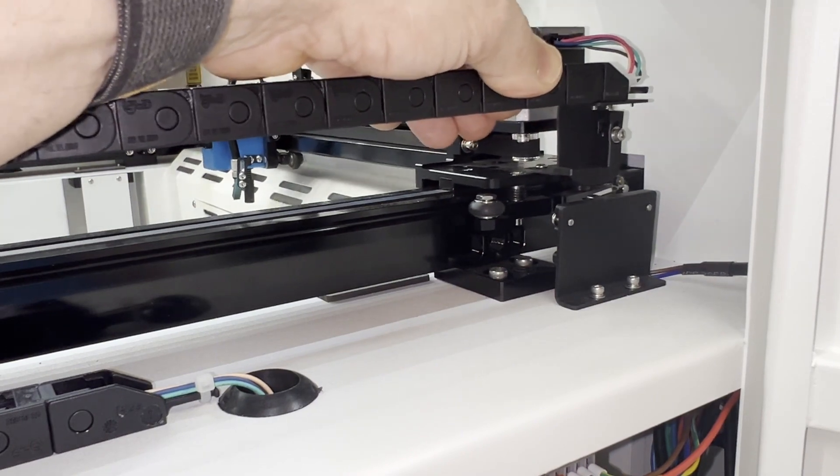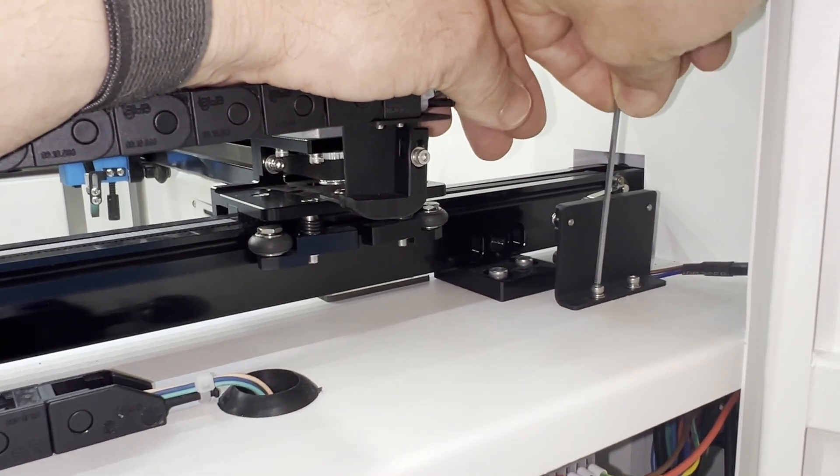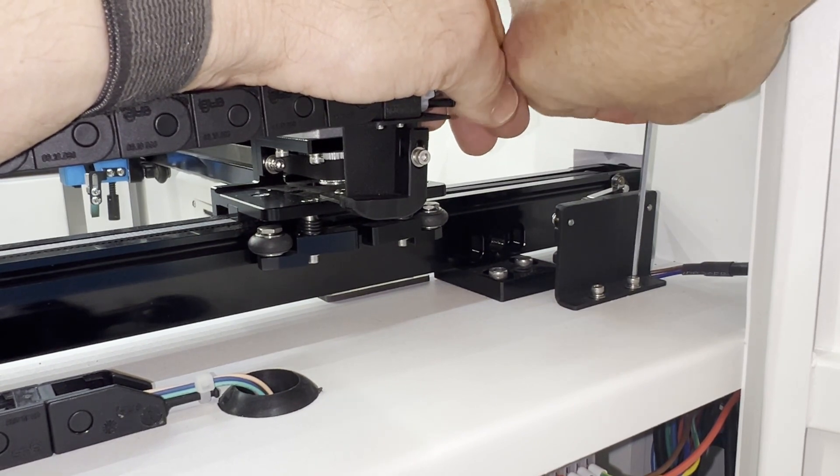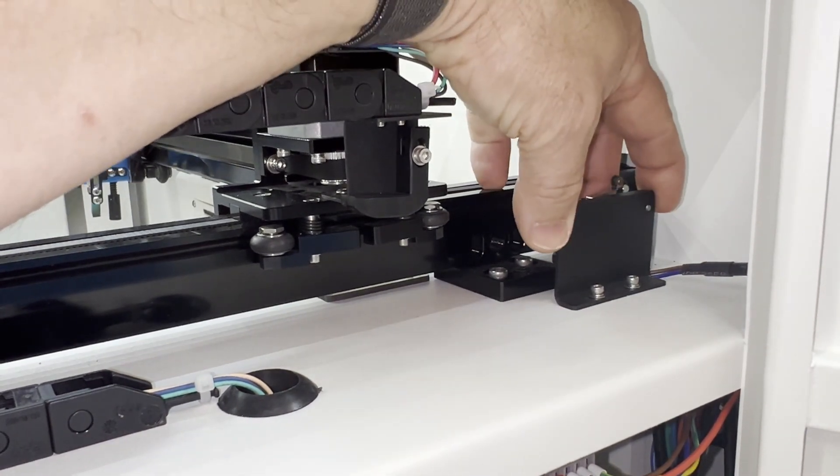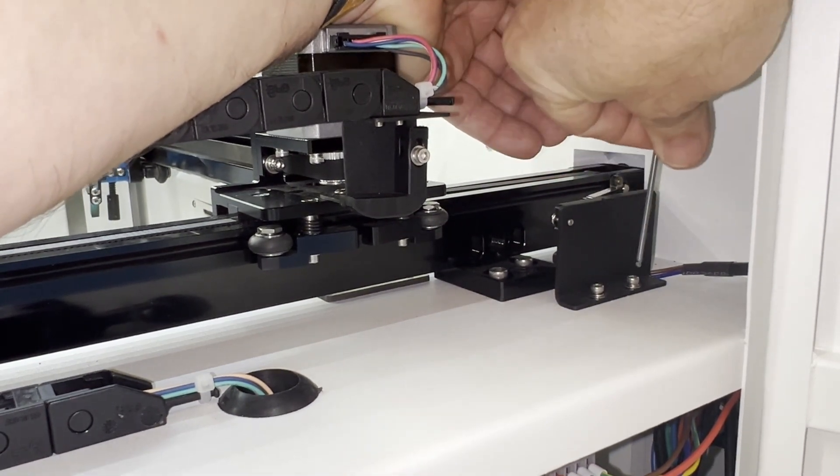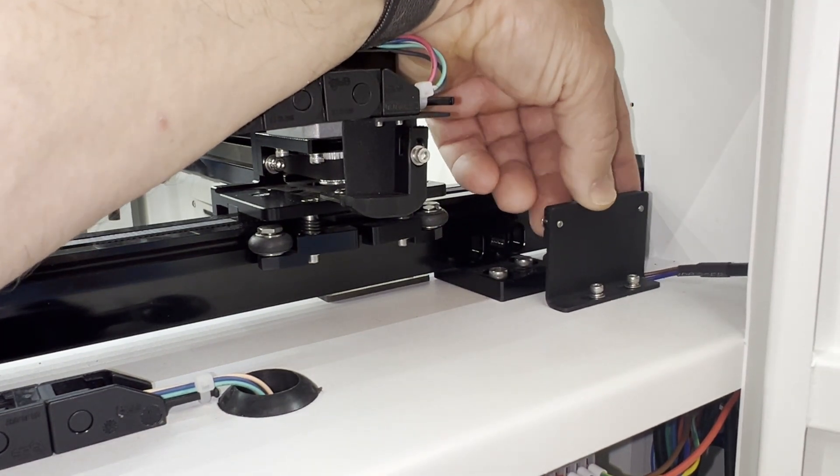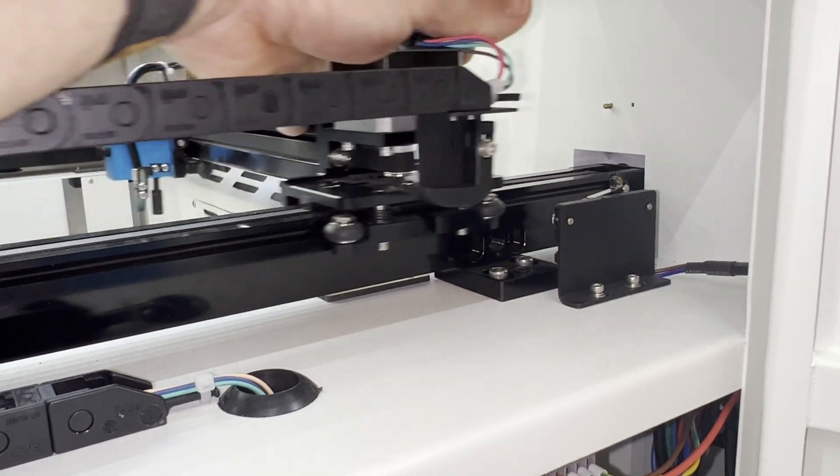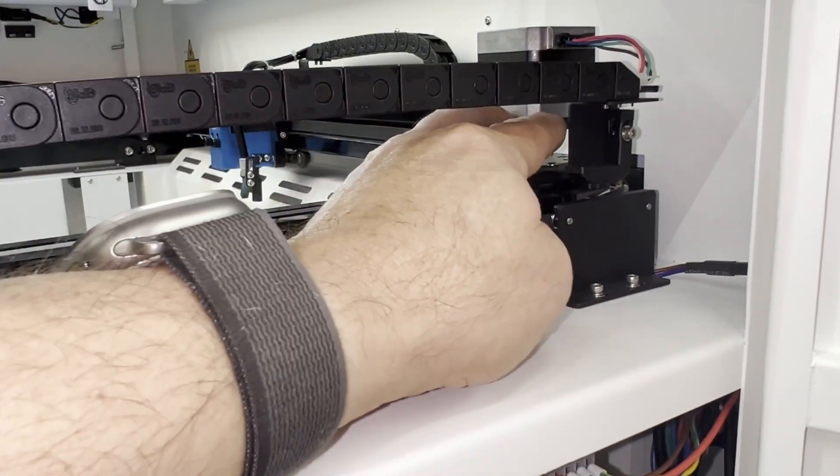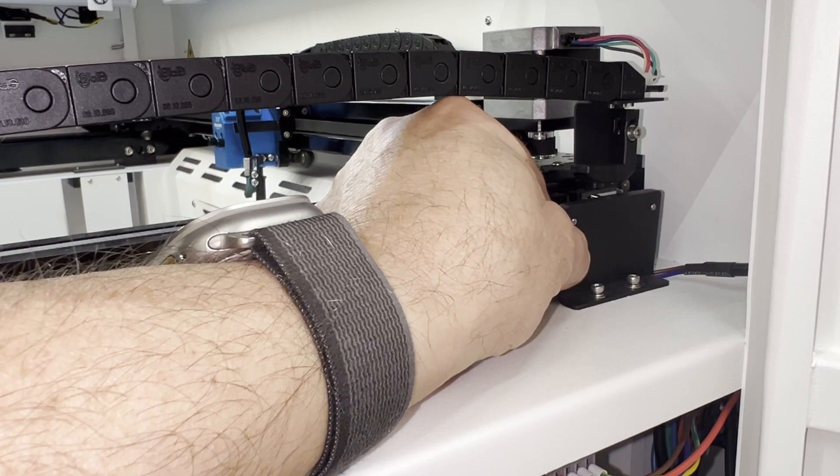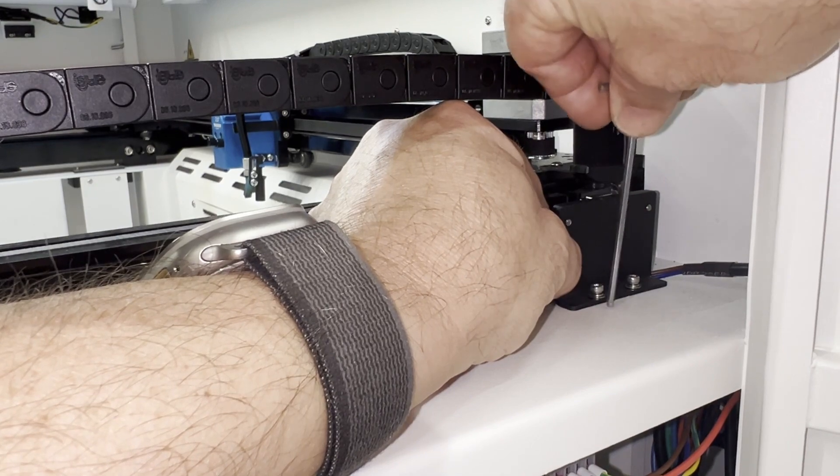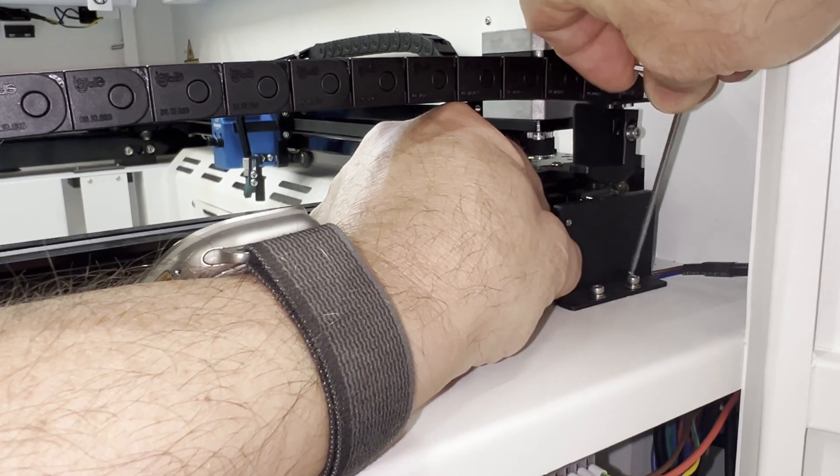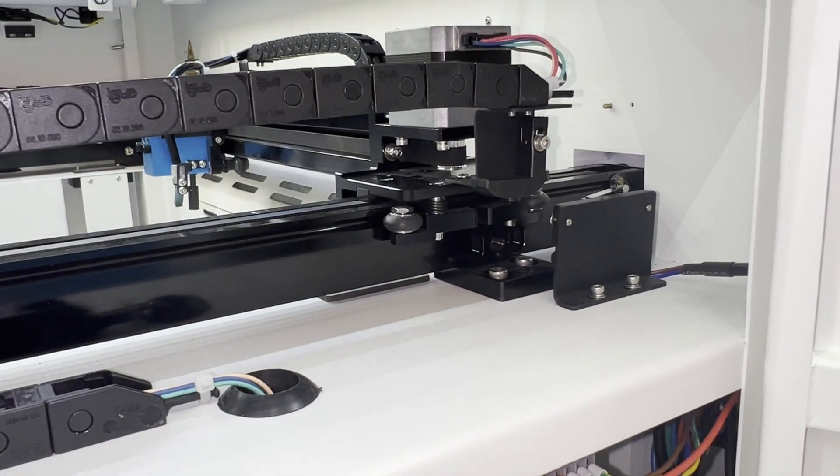So at that point, we would adjust accordingly, and then tighten it down. And we can hear it making contact now. Also, there are two Allen bolts on the bracket that holds the switch itself. Now we can loosen these and they are channeled. And what that means is that once it's loose enough, might take a couple turns to loosen it up enough, but this can slide forwards and backwards as well. And we're just trying to make sure that we are reaching this switch. See, so right now it's not. So if I pushed it and pulled this forward a little bit, you can hear when it makes. So I'll move it just a little bit more, and then I will secure it down.